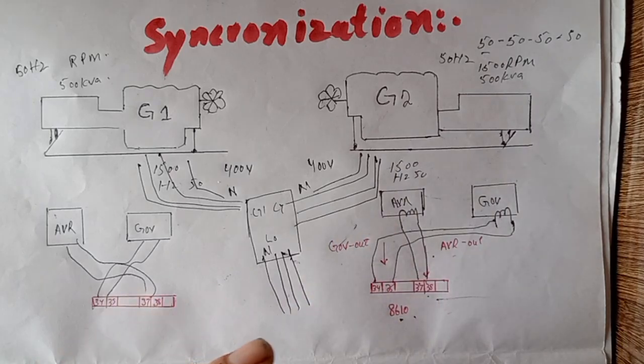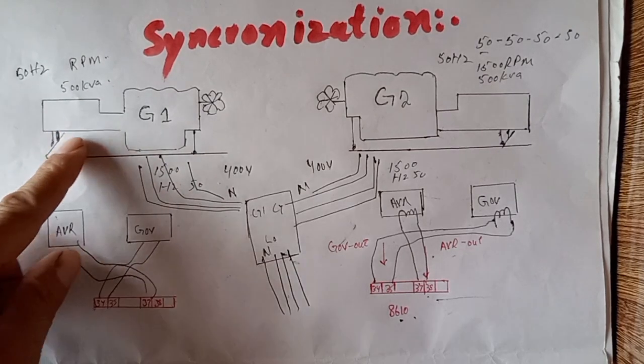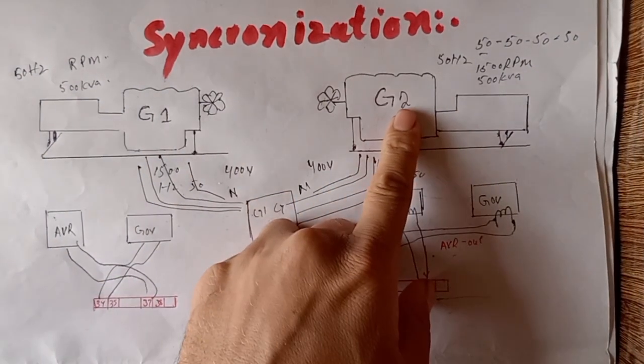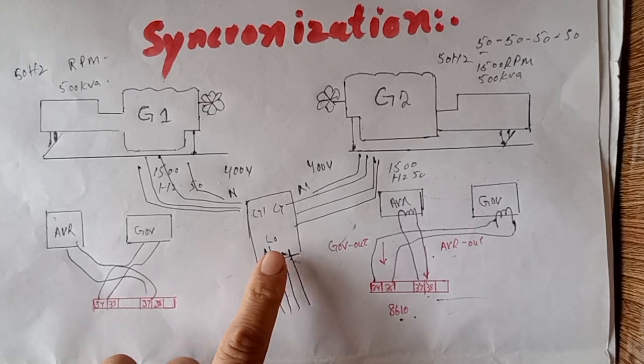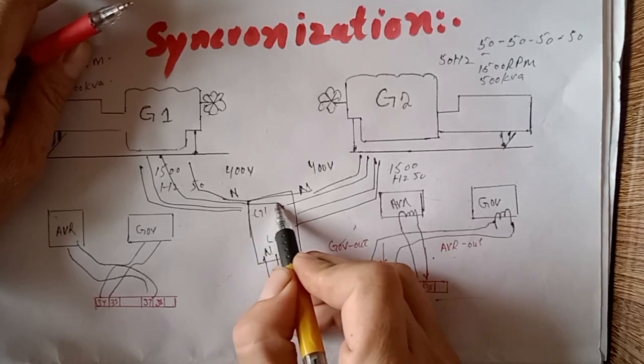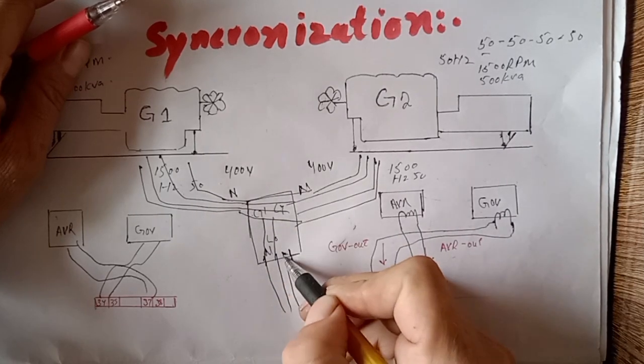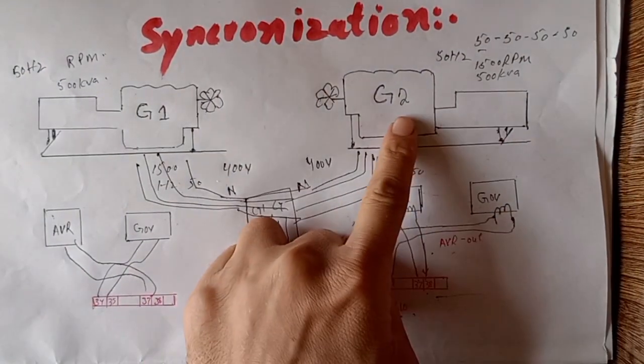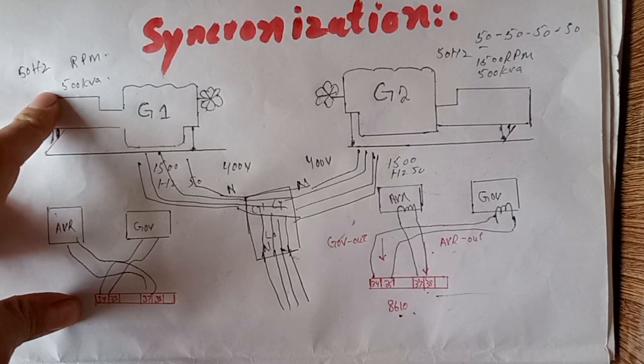This is the complete and proper synchronization of both generators. Both generators must be at 400 volts, 1500 RPM, and 50 Hz frequency. You can easily match the load of both generators. Connect neutral to neutral, L1 to L1, L2 to L2, L3 to L3, and neutral to neutral. The alternator connection must be the same — three phases and one neutral wire for each generator.